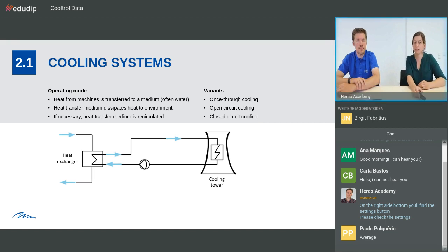There is also another option, closed-circuit cooling. In this case, you can see already there's no make-up water. This is because the water is now not passing openly in contact with the atmosphere through the cooling tower, but it moves in the bundles of a heat exchanger. That means it has no contact with the atmosphere. There is no evaporation, so practically no water loss if there is no leakage. On the other hand, the disadvantage is, in this case, you have a less efficient process because evaporation is not available as a form of cooling anymore. So less water loss, but also less efficiency. What's the most common one of those? I would definitely say open circuit. That's what we are also going to be talking about.